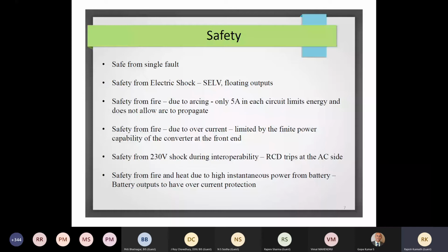We are saying that the 48 volts derived is going to be completely isolated from earth. So if you're going to have an installation from a PV panel, the positive and negative will be coming directly from the panel, and there will not be any connection to earth. And it's actually a similar case if you use a battery as well, right? If you use a battery, you will have isolated voltage from its terminals.